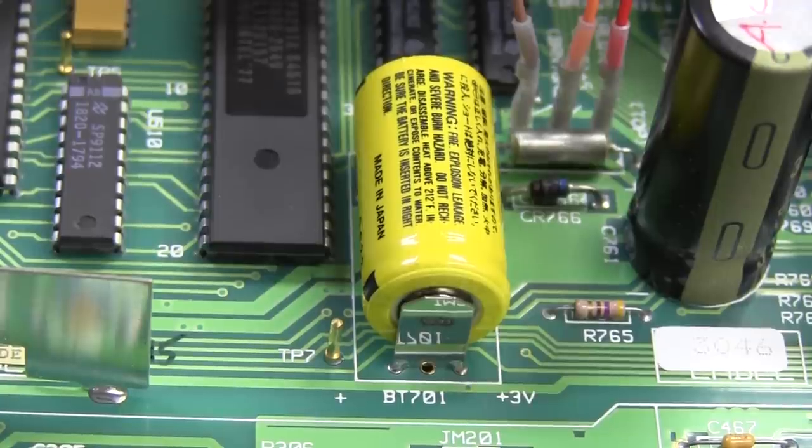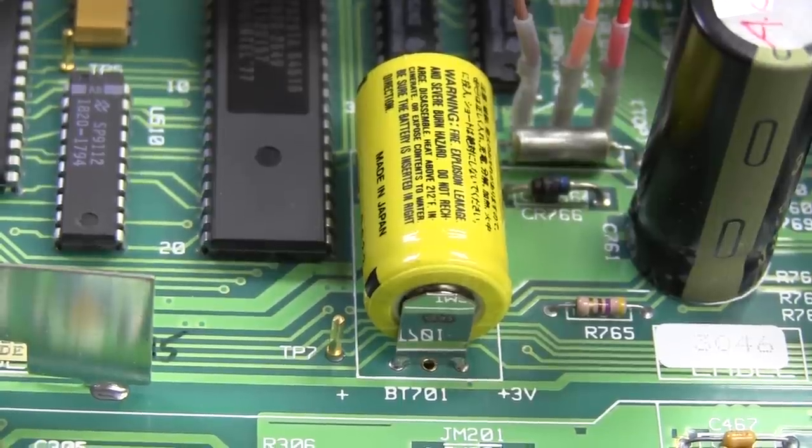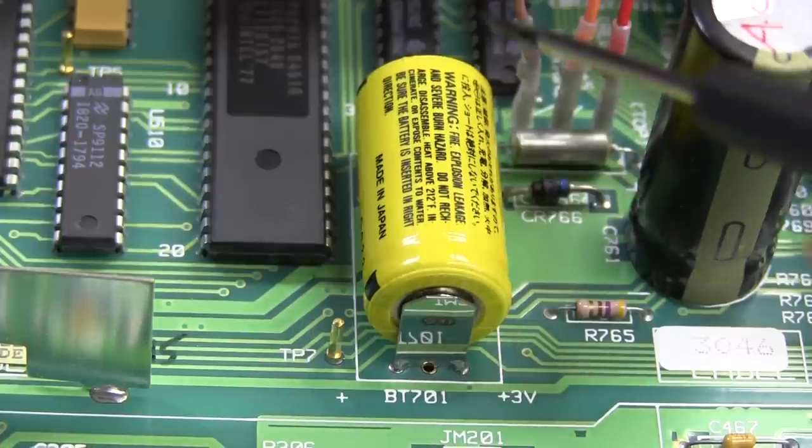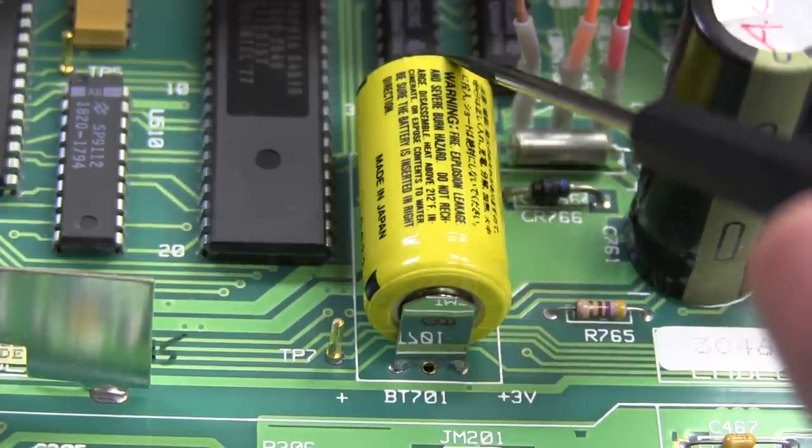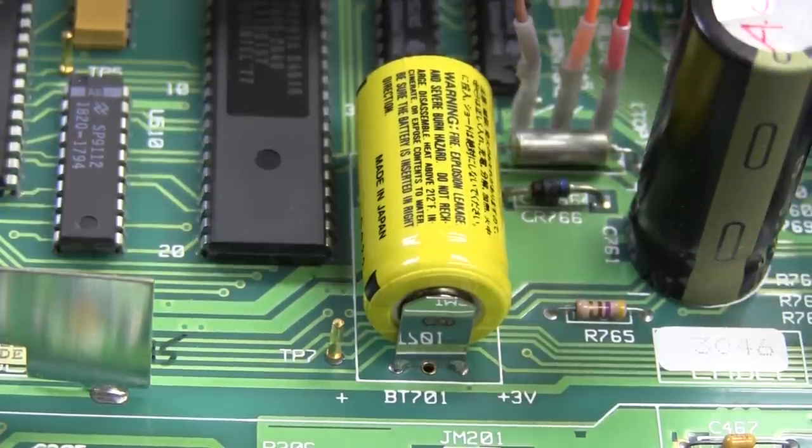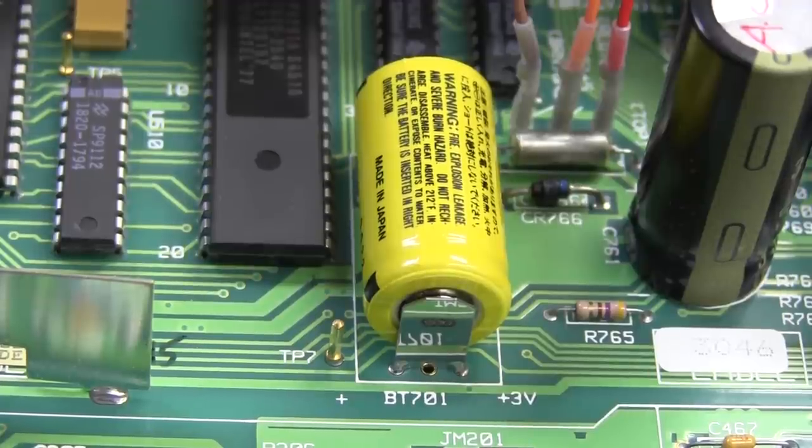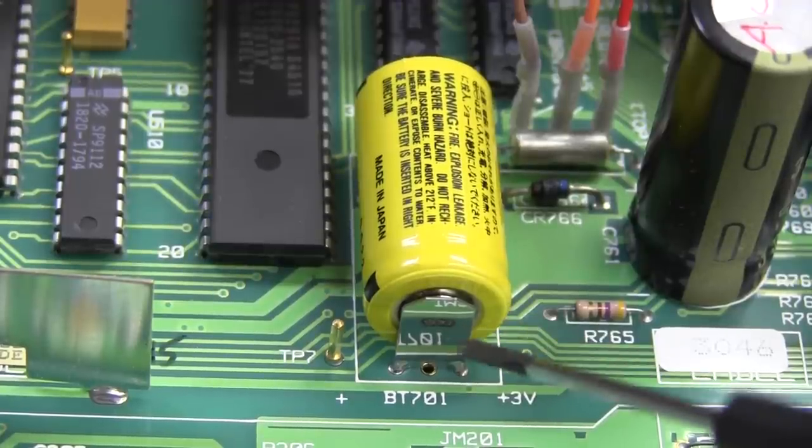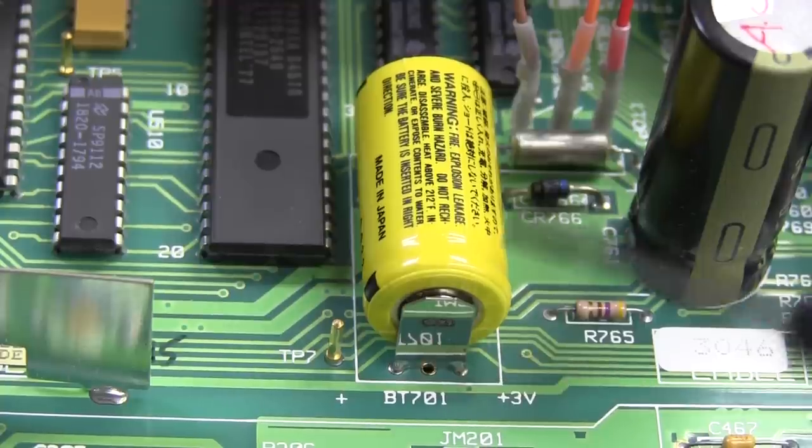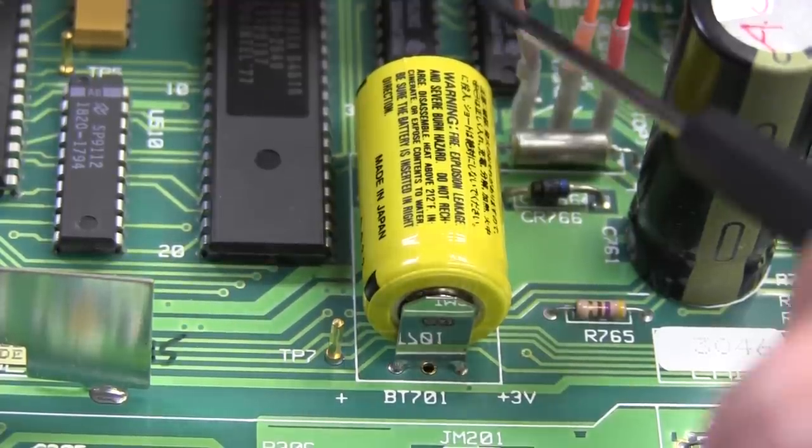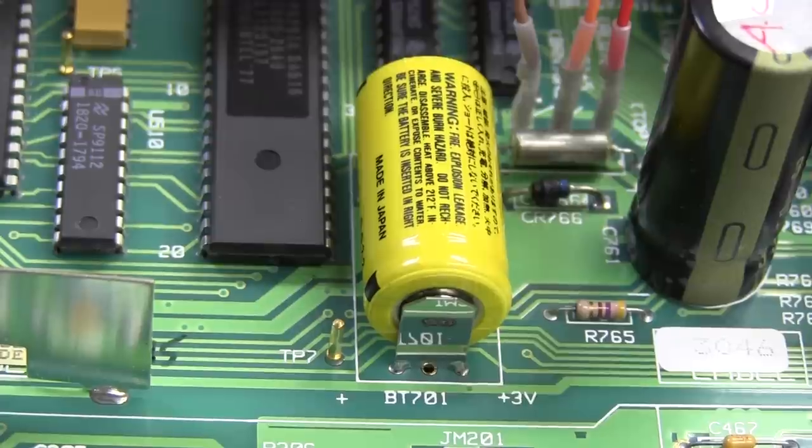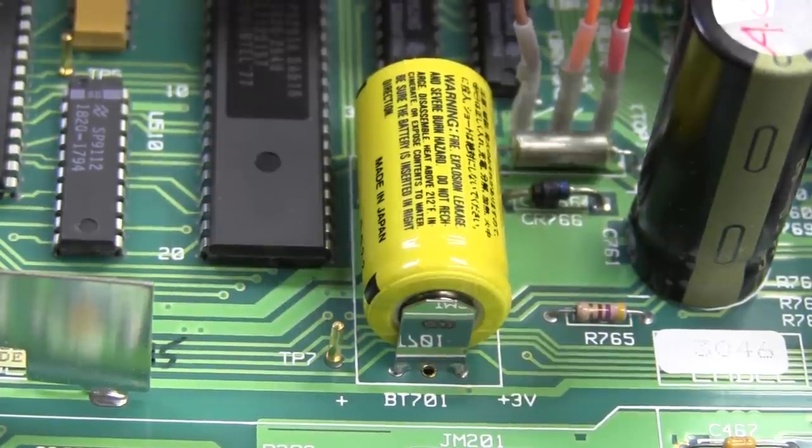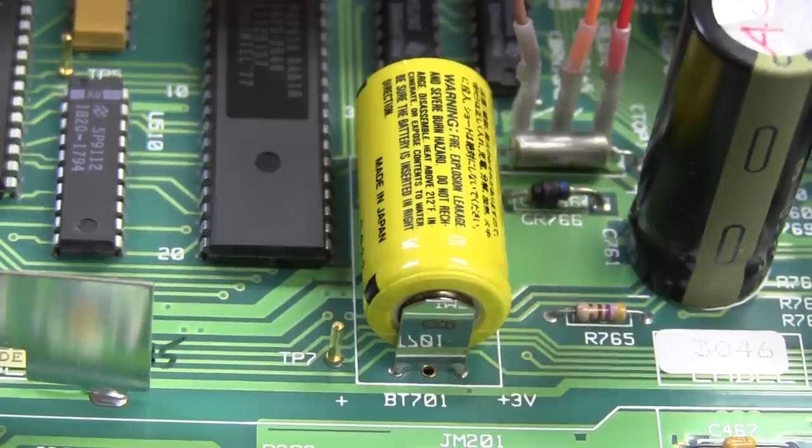Really, when you're replacing these batteries, you need to be very careful because the negative terminal on here, which is up here, is going to be mains-earth-referenced. If you use your soldering iron, for example, even if you power this thing on, if you leave the power on when you actually solder it, it might be okay. This soldering iron goes on the negative terminal over here, it's all mains-earth-referenced. You're not going to do any damage at all. But if you then place your iron on this positive terminal over here, bang, you've just shorted it out to mains-earth and directly back to the negative terminal. You've shorted out the battery, and you could potentially, if you're not careful, lose your calibration constant.